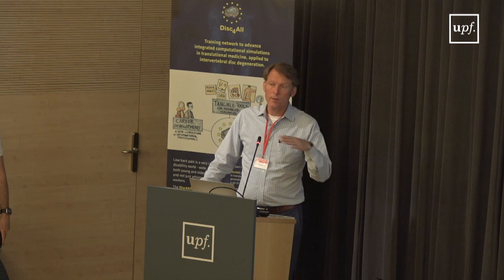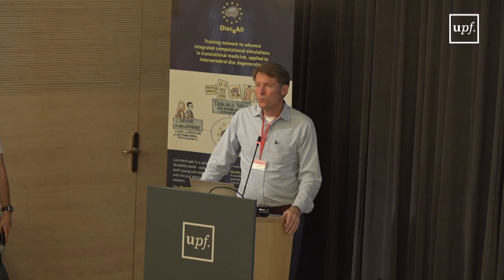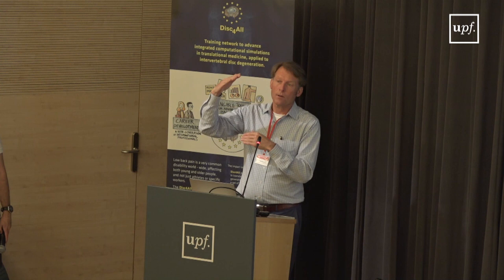The other word we use sometimes, which you might find helpful, is end-to-end example. There is an end-to-end example I'm working on right now with a couple folks from FDA and then people in industry, and we're doing one for the compression bending testing for the F1717 standard for a spinal implant. We're doing every step. We're doing the experiments. We're doing the simulations. We're filling out the V&V 40. We've done it all. We even did hierarchical validations. We published one paper already on how to model rods, and now we're modeling the full assembly.